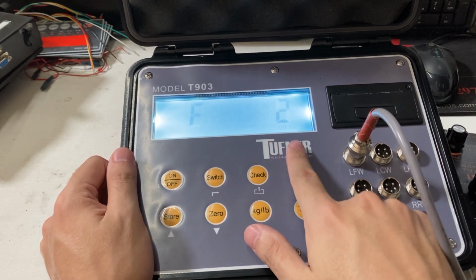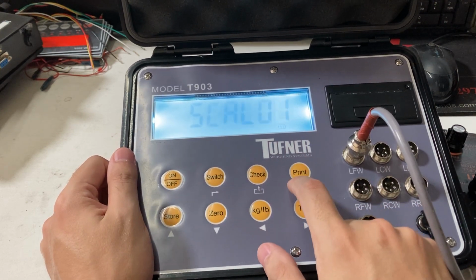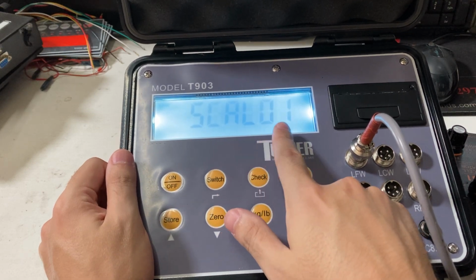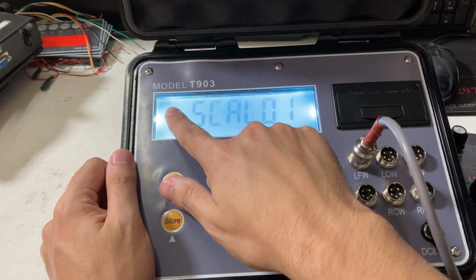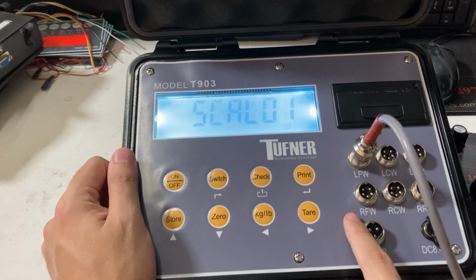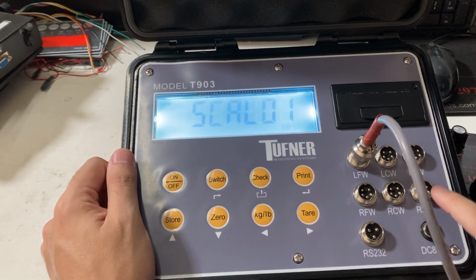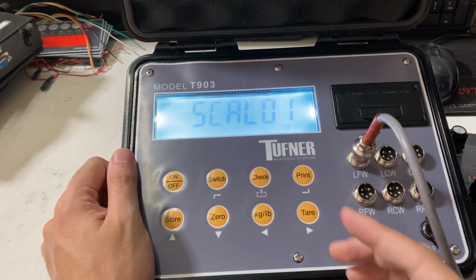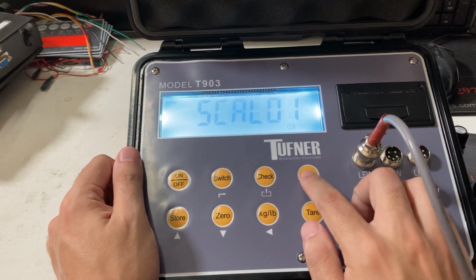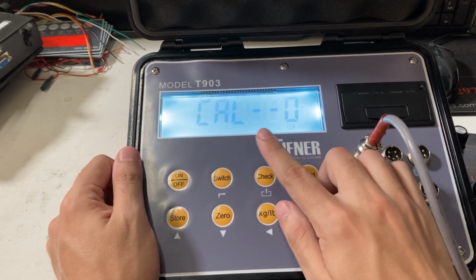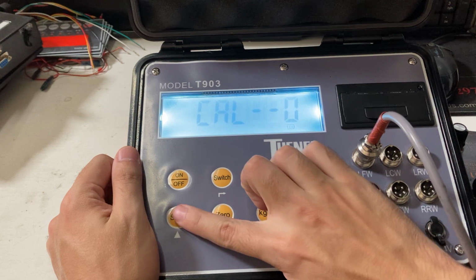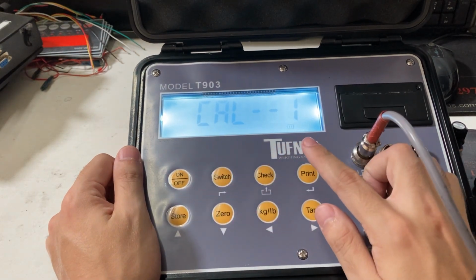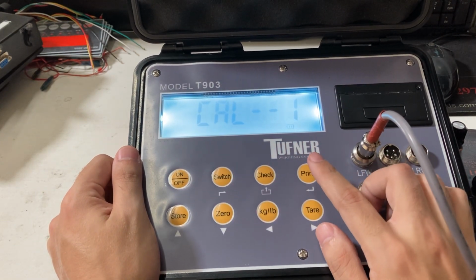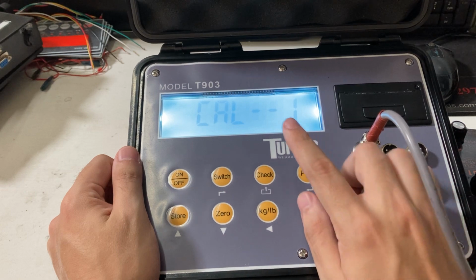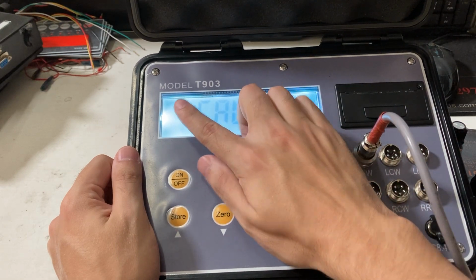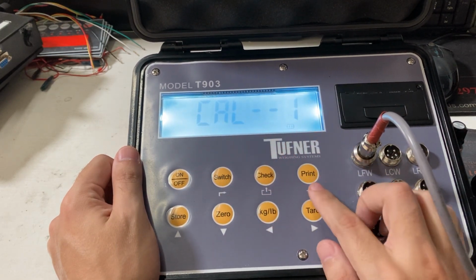Now F2 actually starts calibrating the pads. So you see scale 1. Remember, scale 1 is LFW, see up here. 1, 2, 3, 4, 5, 6. So right now do scale 1. And then cal 0, you set it to 1 for 0 calibration. So when nothing on the scale, make sure that LFW is nothing on the scale. Cal 1, you press print.